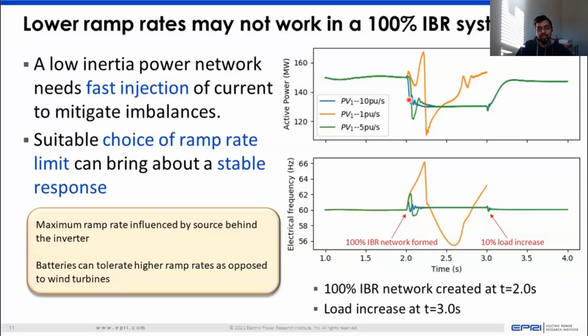What one also needs to be concerned about is that these ramp rates are actually influenced by the source behind the inverter, which means that a battery energy storage system could tolerate a higher ramp rate as opposed to wind turbines, which have mechanical components and can only tolerate a lower ramp rate. And if we are going to evolve into a system where we want inverter-based resources to provide services in terms of arresting frequency decline and helping the frequency stay away from the UFLS, then we need to pay a lot of attention to this ramp rate value, because it can have a large potential impact on the system.